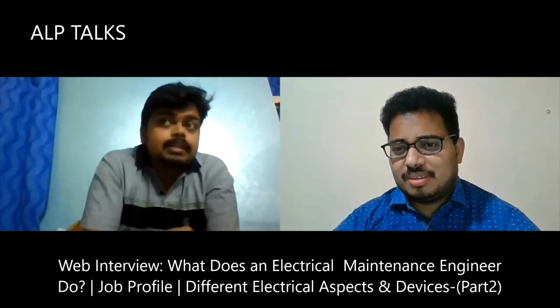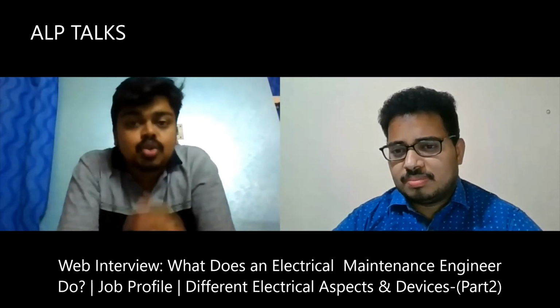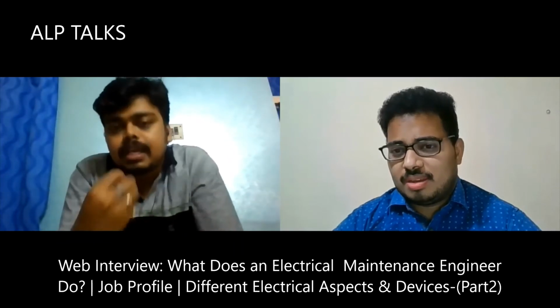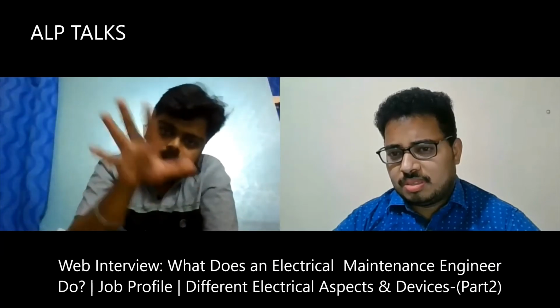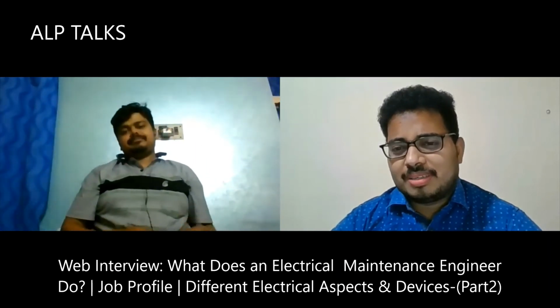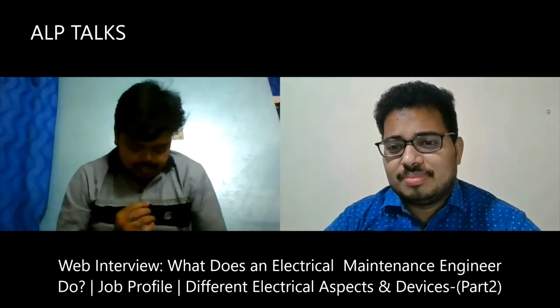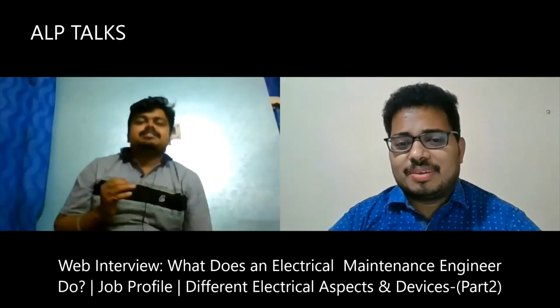Not only these, in substation also you have to put the CO2 isolation system. If any kind of incident happens, CO2 will be emitted on the panel, and the arc or flame will get diminished. So this kind of automation is required. This CO2 system is called a clean agent system, available in manual and automatic versions.